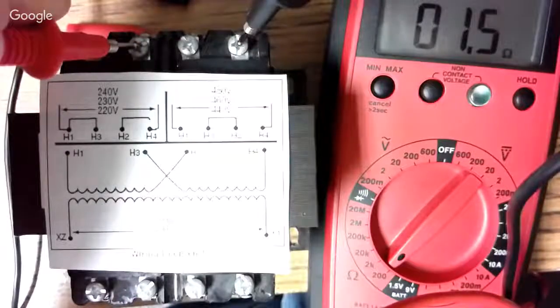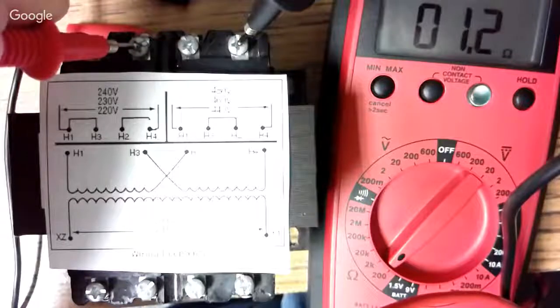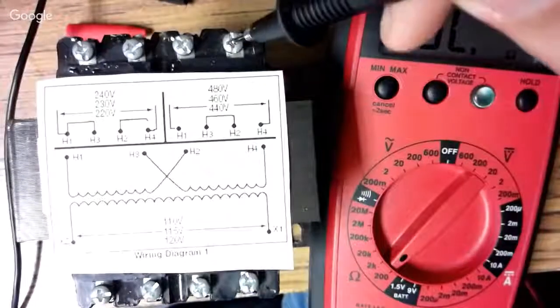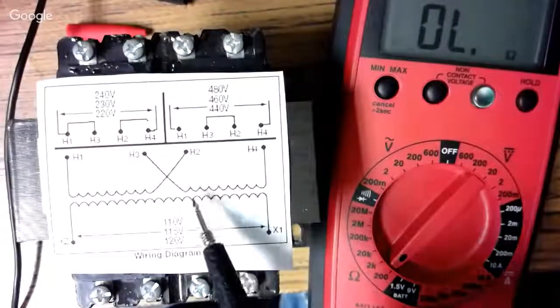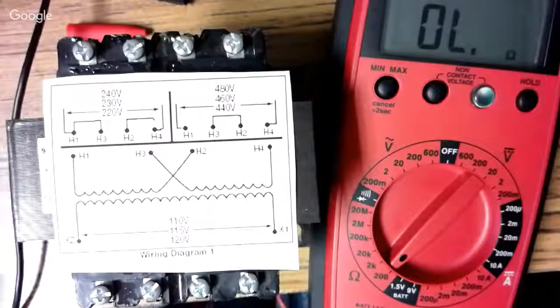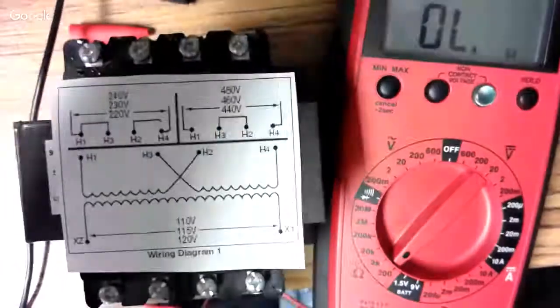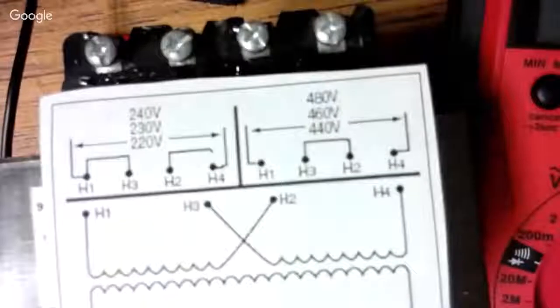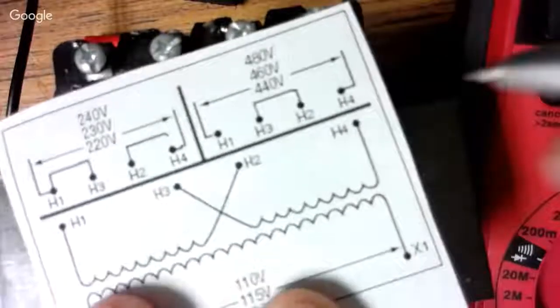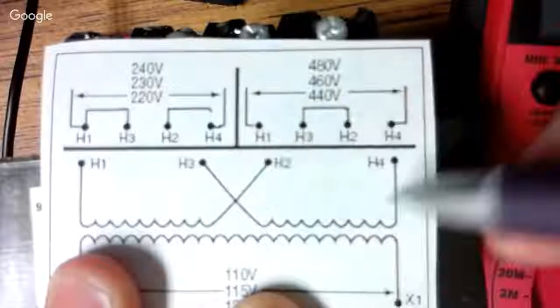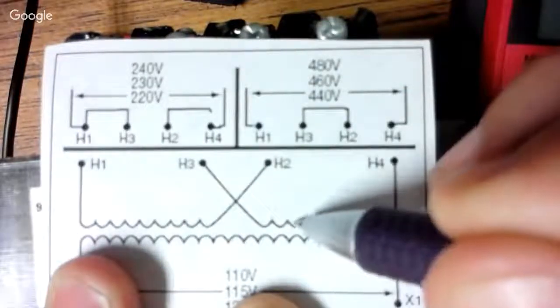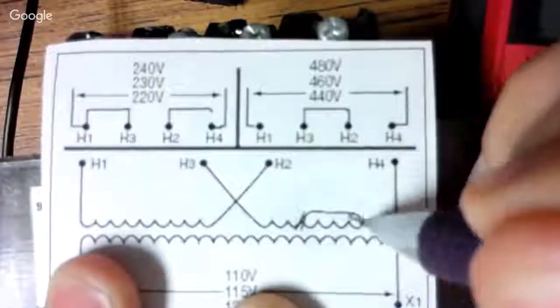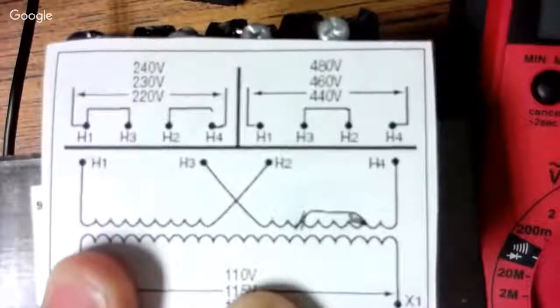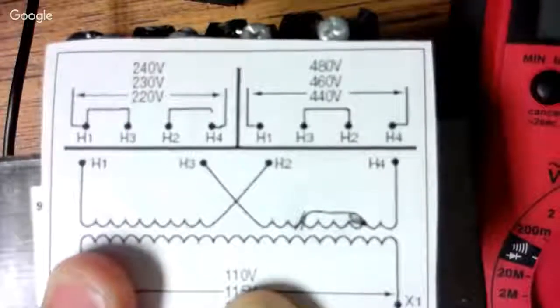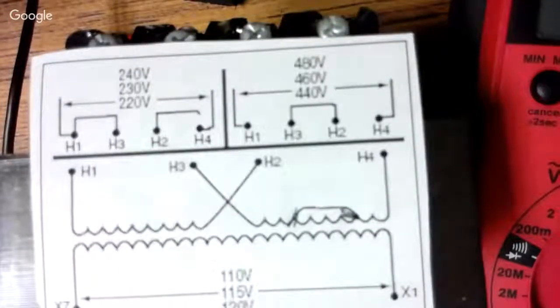And as I wait for it to stabilize, I see that it has settled at 1.3 ohms, which tells me, if I check the ground, I don't see anything that tells me that H3 and H4, somewhere in this coil of wire, is a short, and so it's actually jumped somewhere inside there. Because of the imbalance, I have less resistance, which tells me that somewhere on this H3 and H4 the coil of wire is shorted. And so if I look at that, I'll see there's a jumper here. That means that part of this coil is null and void because it's a jumper. There's a short inside this transformer, which means it is no good and it's time to recycle it.